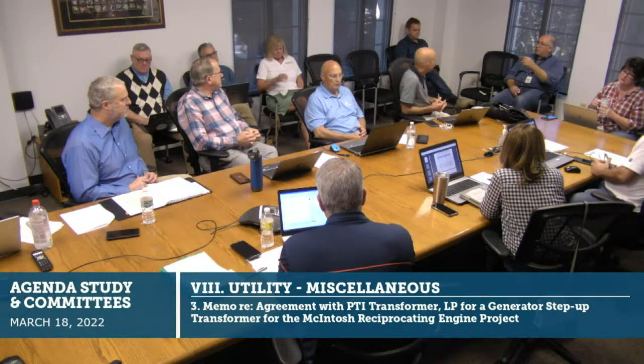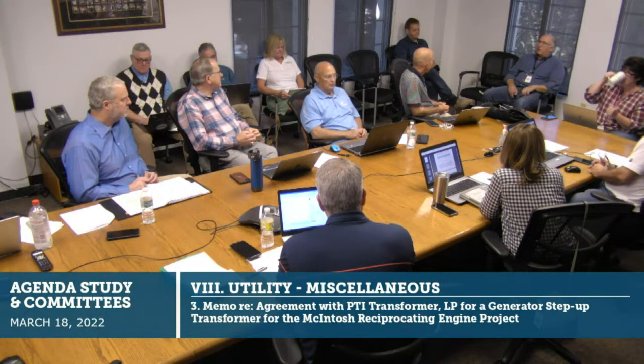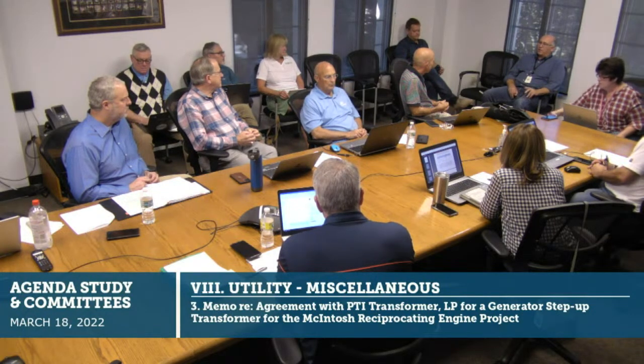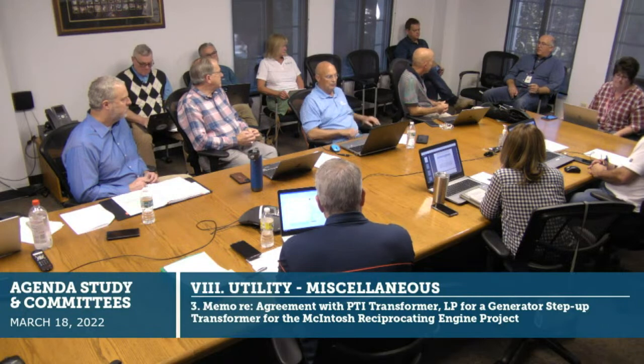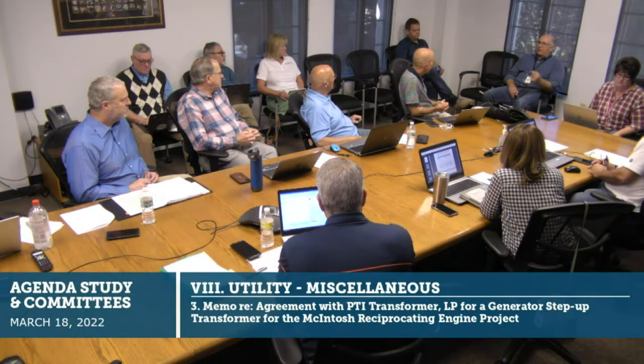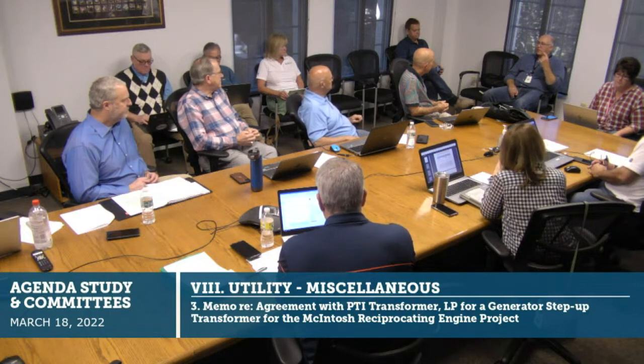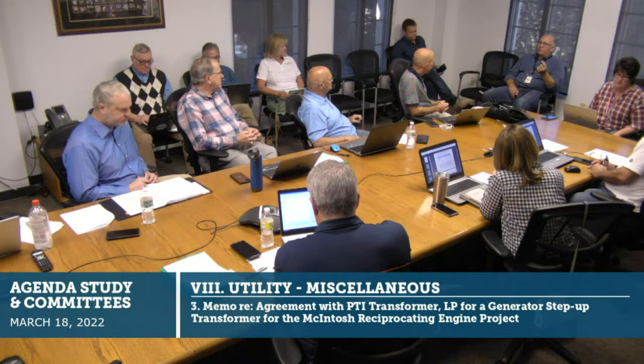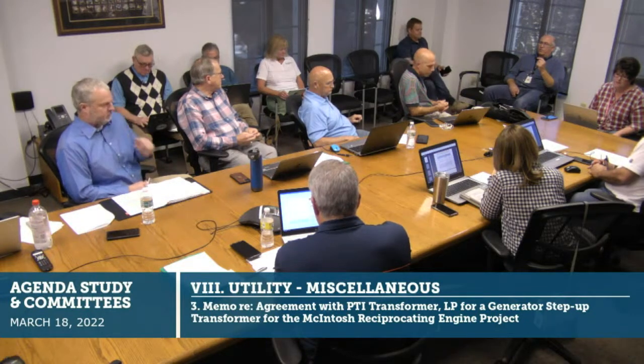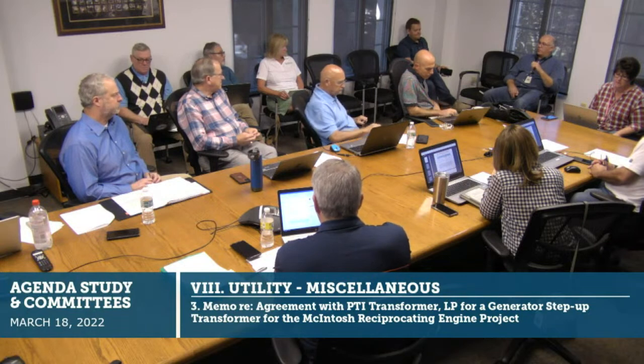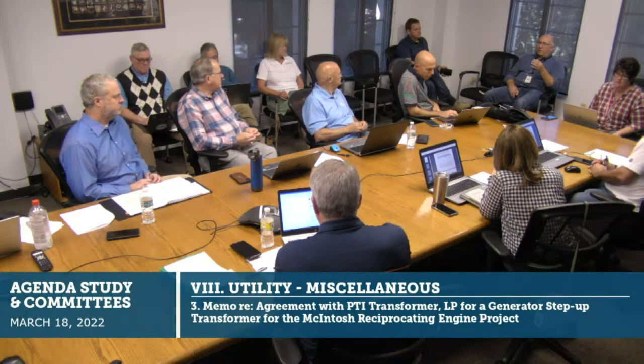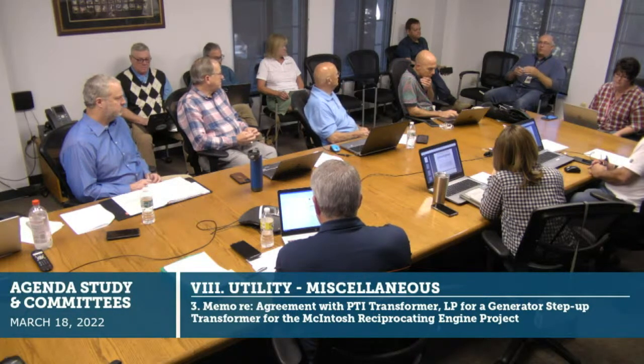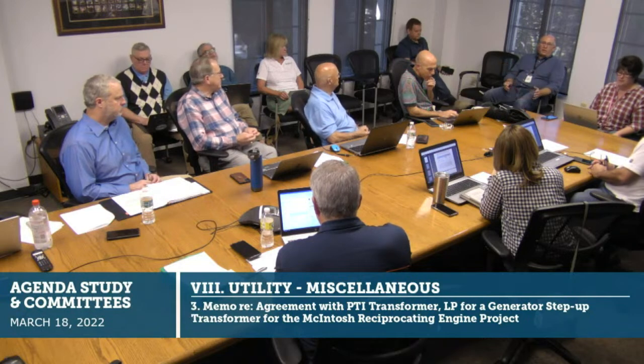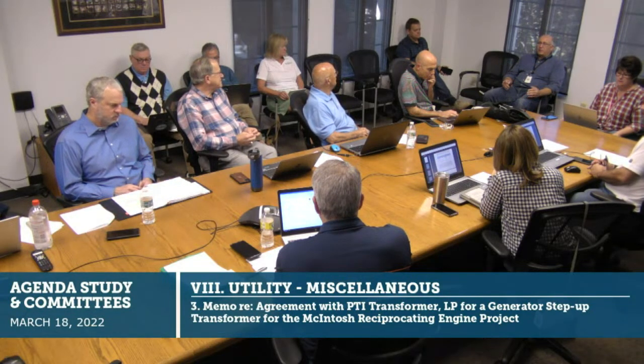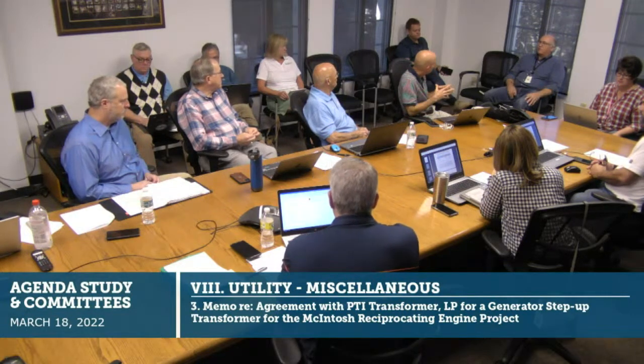Yeah, exactly right, Mayor. We have 2 secondaries, and the reason why we brought in 2 secondaries is, one, for the safety aspect. By having the dual secondaries, that makes less risk and exposure to the employees when they're doing switching operations for arc flash, which is very dangerous. So that's one reason. It also gives us the ability from a maintenance standpoint to take down half the plant, do maintenance, and still keep half the plant running, where before we couldn't do that. So the only time we'd have to take down the whole plant is when we're doing this transformer testing. That's advantageous to us.